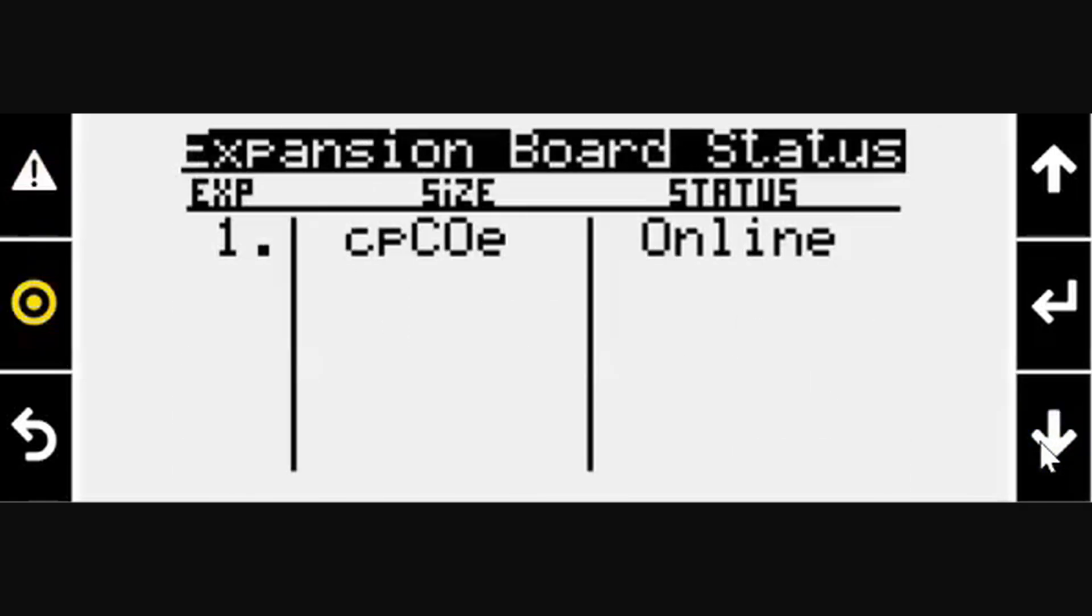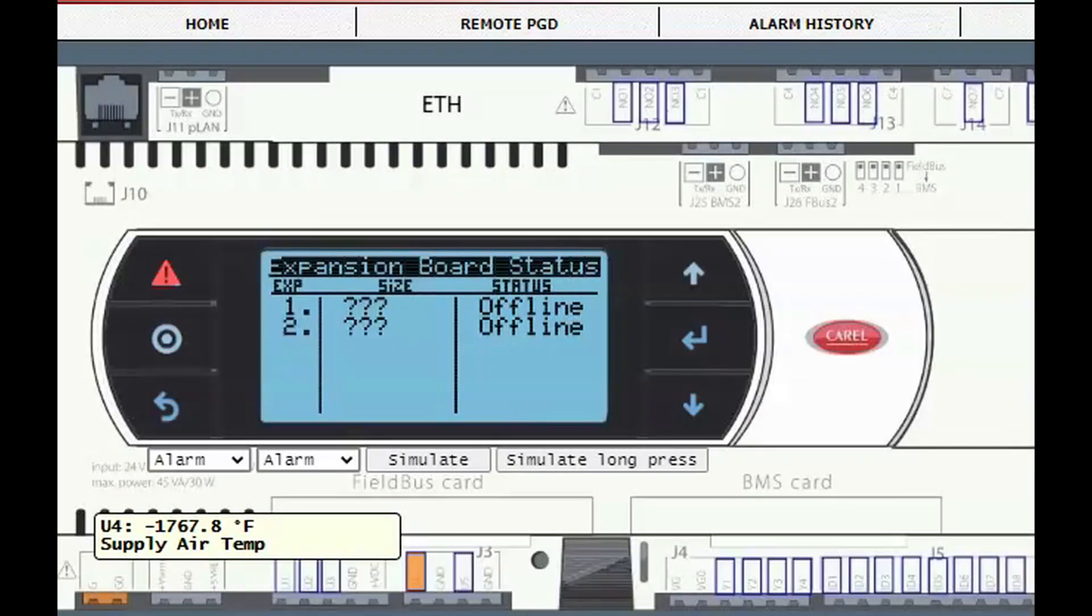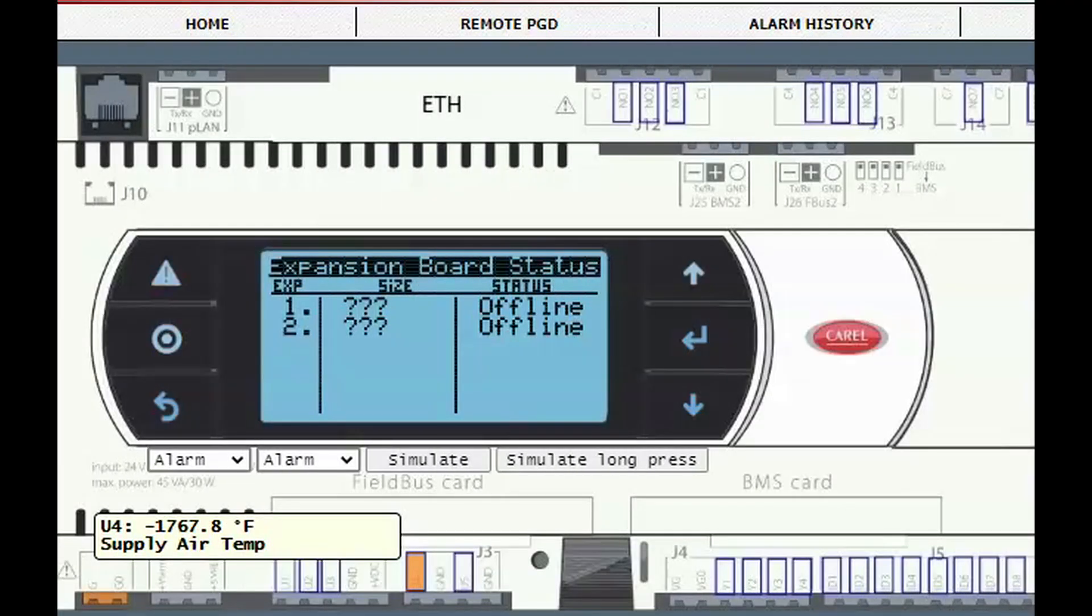If the expansion is still showing as offline in the unit status menu, it may need to be addressed using the addressing wizard. If the serial number of the unit starts with a 2 or a 7, the following steps may be required. On the controller interface, push the target button to go to the main menu.